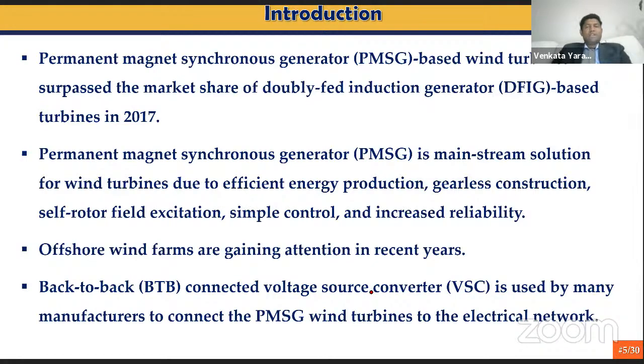Permanent magnet synchronous generator is the mainstream solution for many reasons: efficient energy production, gearless construction (one of the main attractive points for offshore wind turbines), and it doesn't need any excitation since the permanent magnets provide the excitation. The control of PMSG is much simpler than squirrel cage induction generator or double-fed induction generator, and its reliability is very high compared to SCIG or DFIG generators.